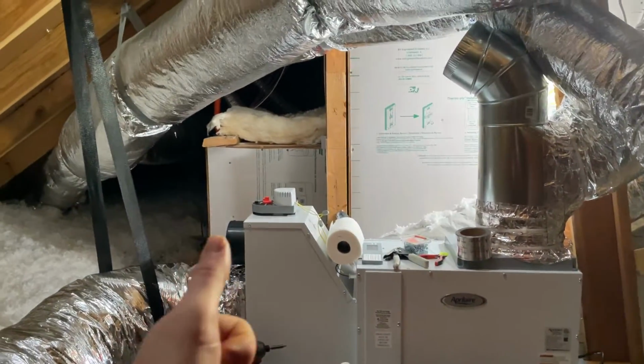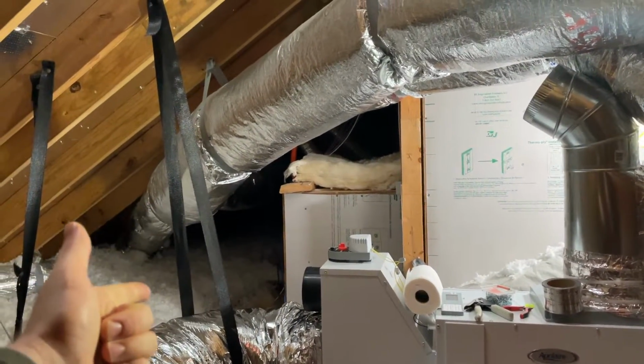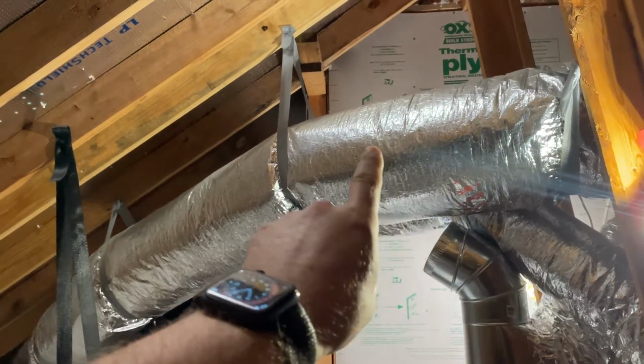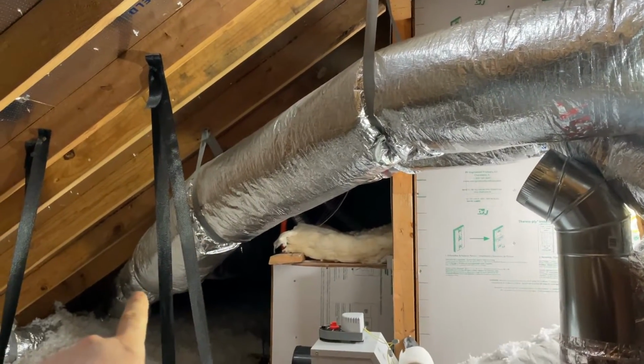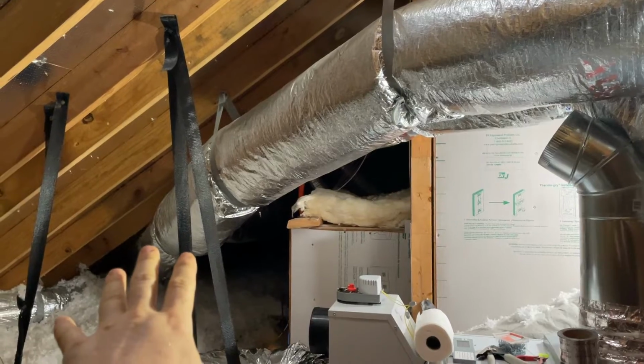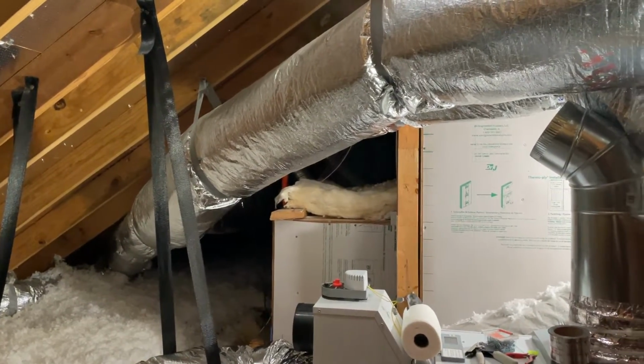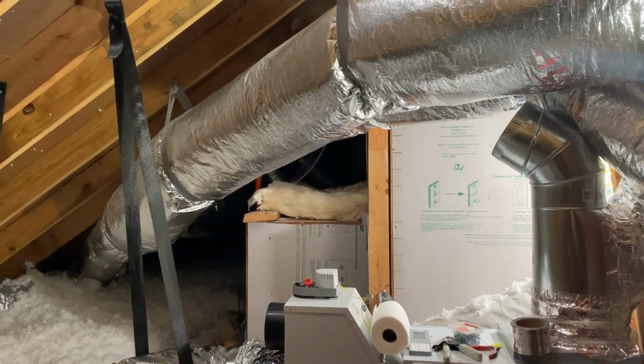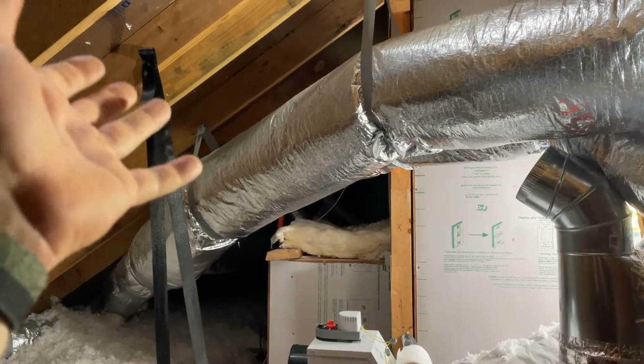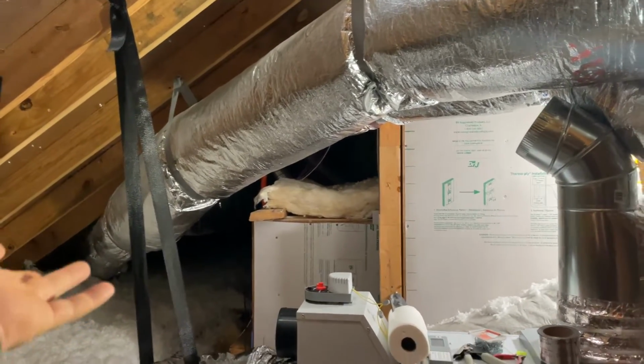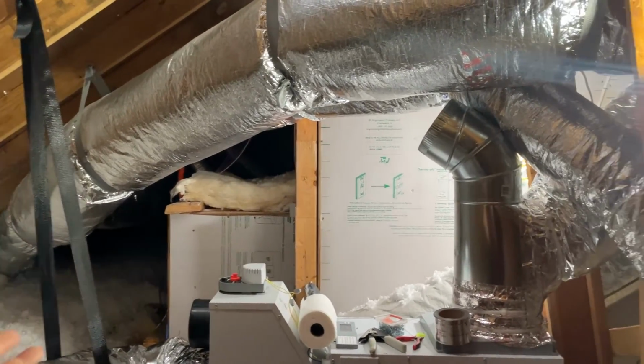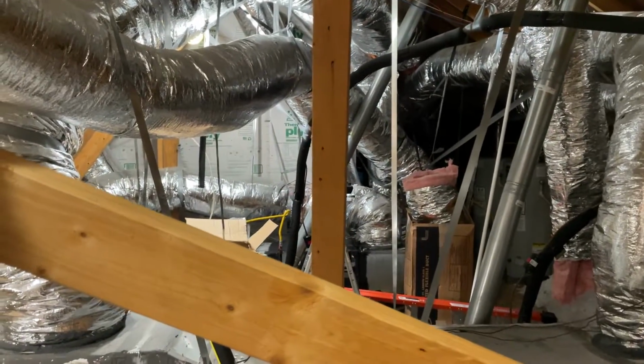Since the bathroom and master bedroom have this one massive 12-inch duct feeding them both, including the master bedroom's closet, the rooms it feeds have way higher humidity than the rest of the rooms that the second air conditioning unit is feeding.